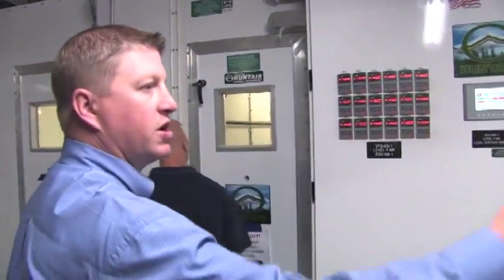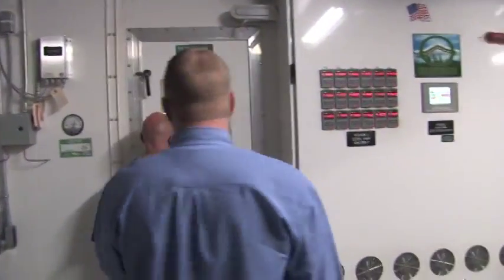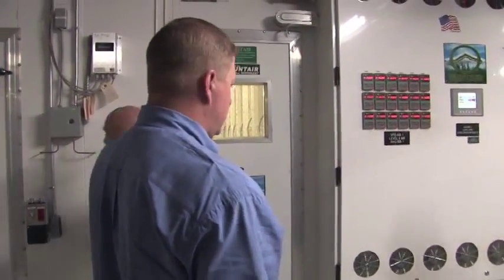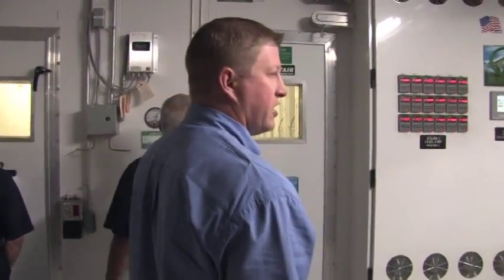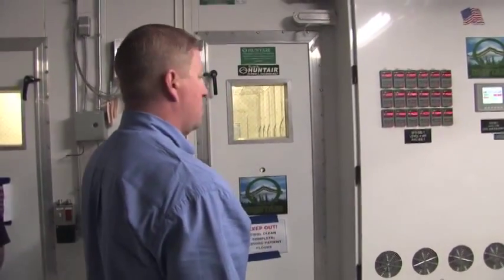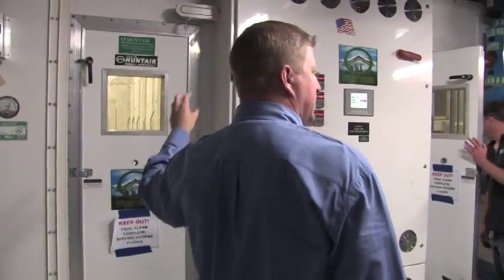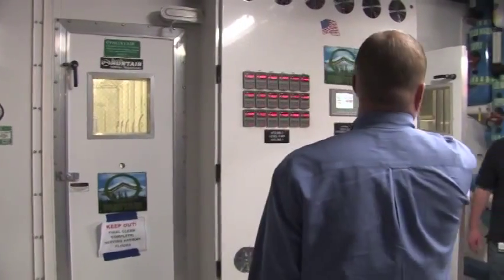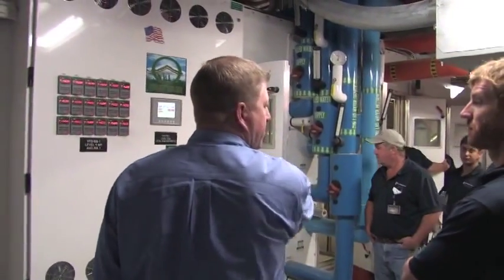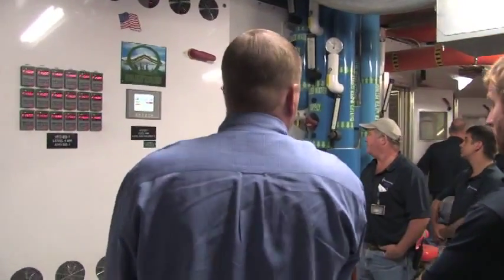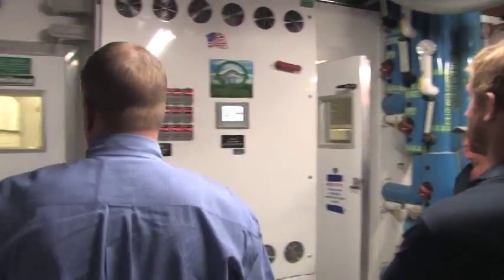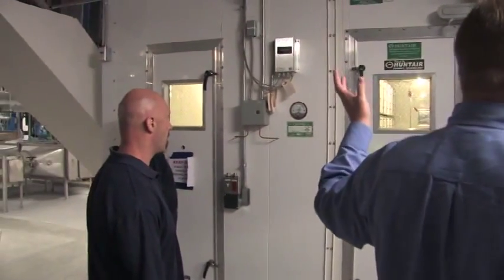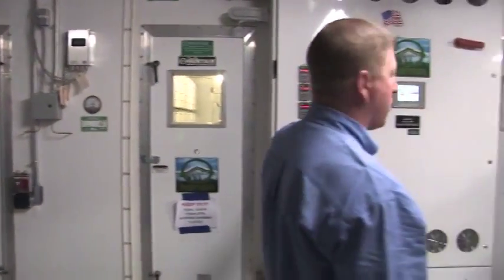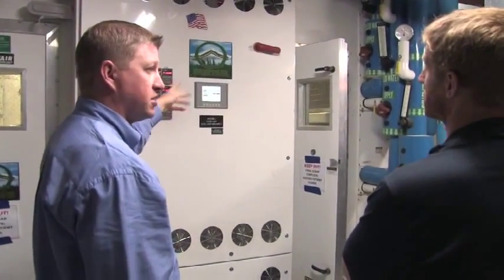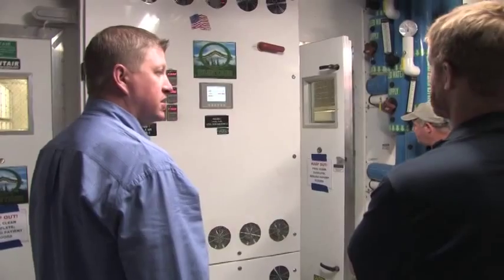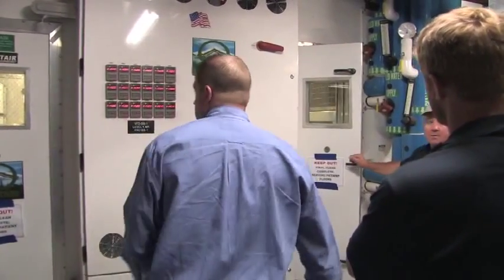I'll double back and get questions on that end. Here we've got the outlet side of the fan wall, the fan array. Any kind of maintenance done on the motors, the fans will be done from this side. Sorry, that side actually as well, I forgot to point out the backdraft dampers. If you have a fan failed or a fan shut off, it will isolate it. And then our discharge plenum. And what we'll do is, if you want, we'll seal it up, we'll turn it back on, and I'll run you through the control screen a little bit so you feel comfortable with that. Does that sound good? We'll just shut all the doors.